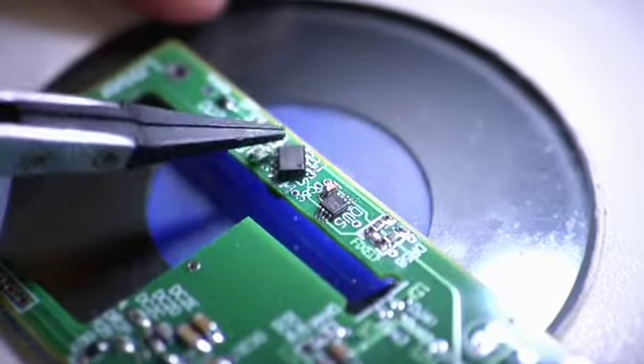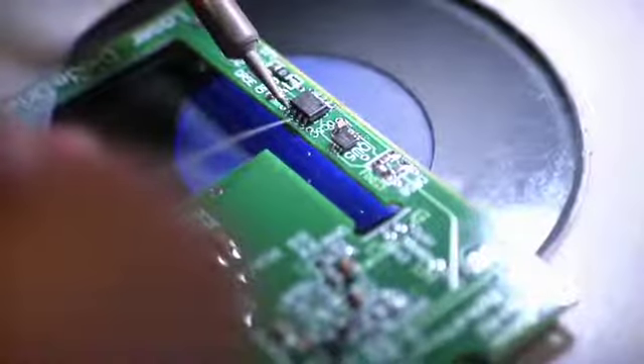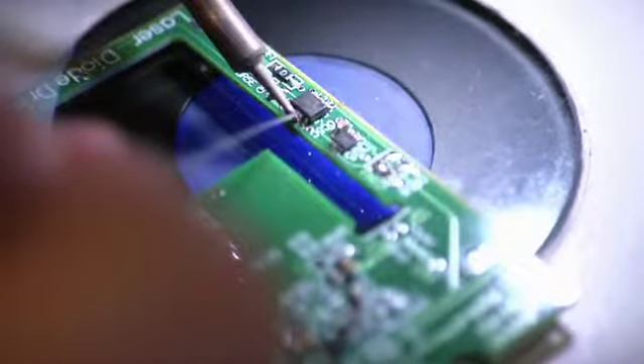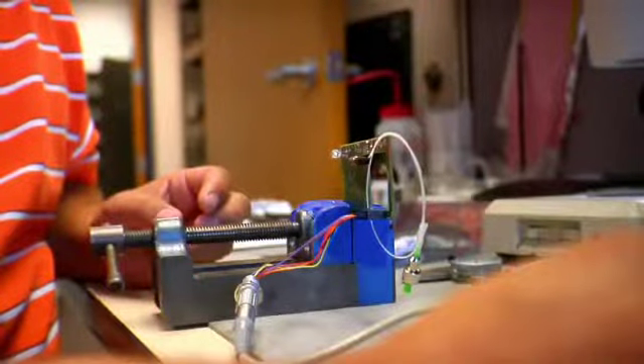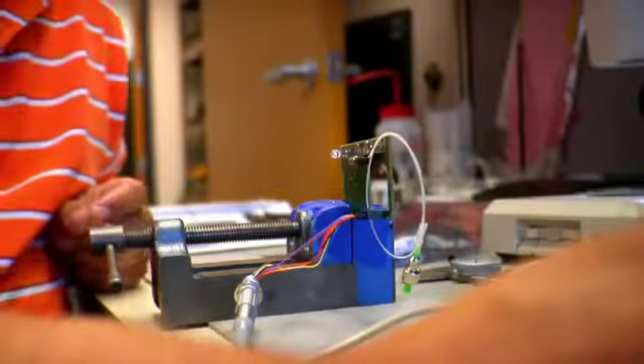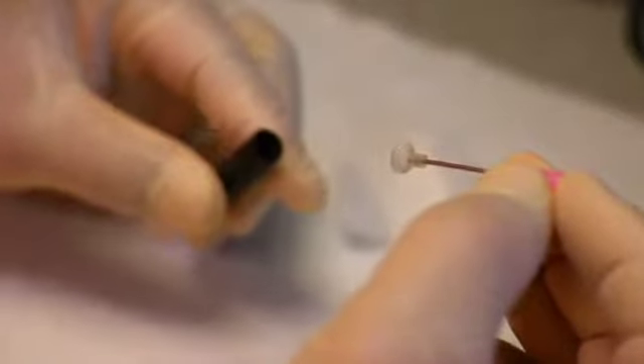But at the time, it was just a perfect point source microscope, a perfect instrument for helping align not only the microscope itself, but the test optics we were going to use to make sure it was put together correctly and performed as expected. We needed an instrument to be able to find the center of curvatures and the axis of off-axis optical elements in our laser designator. The PSM is a very flexible, small device that allowed us to maneuver and find those axes and then bring them to the datums or the mechanical axes of the box, the housings that these optics would go in.